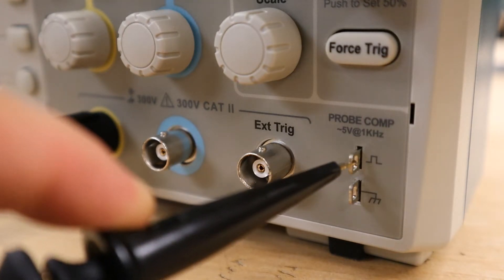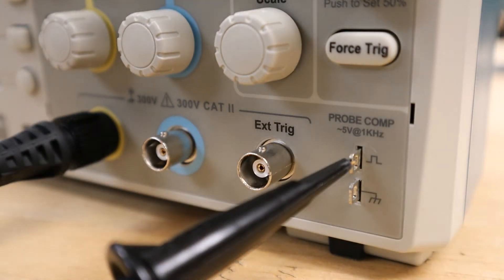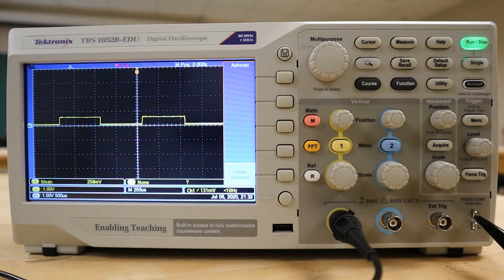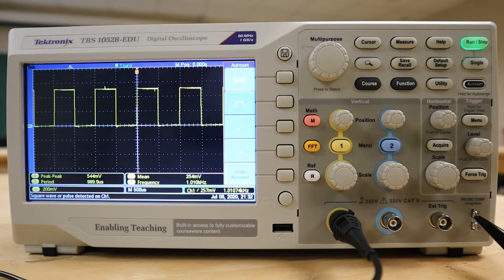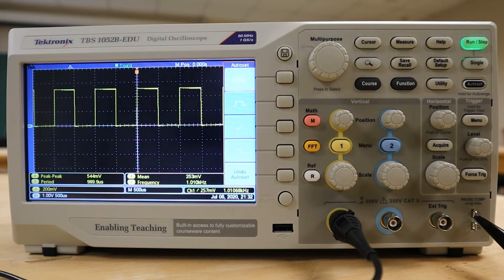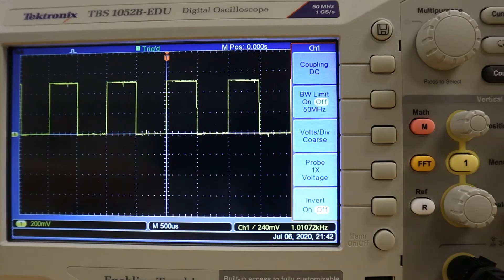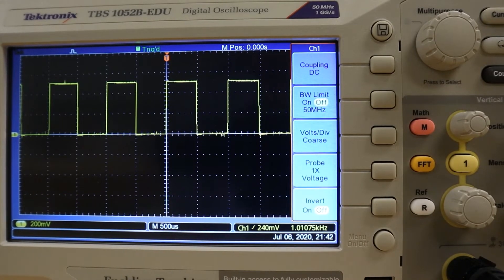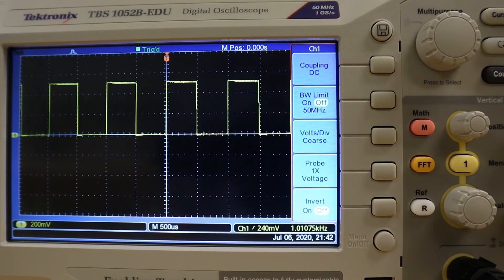In this case, we will connect the hook tip of the attenuator probe to the calibration pin and press the auto-set button. If everything is calibrated correctly, a square wave should appear with a magnitude and frequency as specified by the oscilloscope. If the magnitude did not display correctly, or if no trace was seen, we could drill into the menu for the first channel to locate any potential issues.